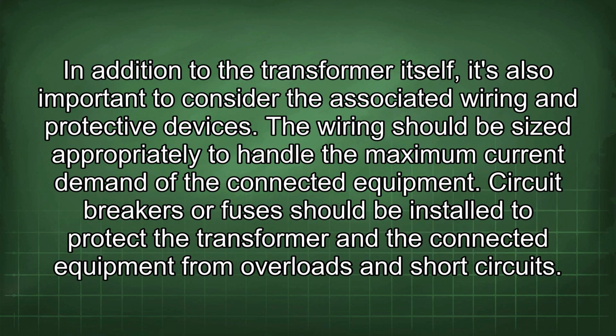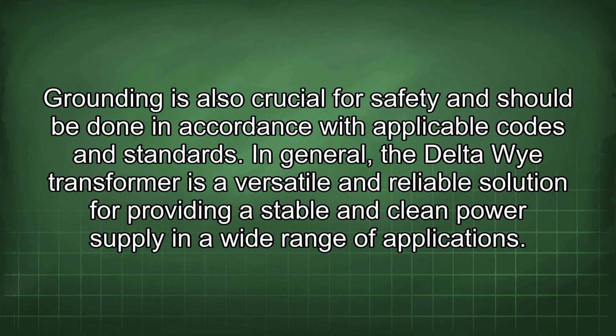In addition to the transformer itself, it's also important to consider the associated wiring and protective devices. The wiring should be sized appropriately to handle the maximum current demand of the connected equipment. Circuit breakers or fuses should be installed to protect the transformer and the connected equipment from overloads and short circuits. Grounding is also crucial for safety and should be done in accordance with applicable codes and standards.